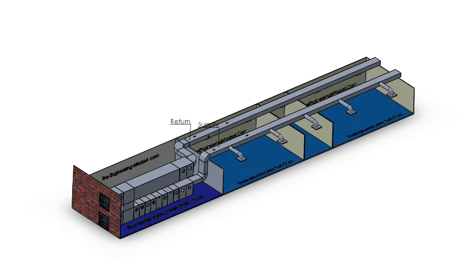CAV systems do have some limitations because their supply air temperature is varied but the volume supply of air is constant. So while this system runs, it provides air at a consistent and constant volume and only the temperature of that air changes. Typically the air is provided at around 13 degrees Celsius, 55 degrees Fahrenheit, but this can be adjusted to suit the needs of the site. The volume is constant, but the amount of air it provides is really going to depend on the size of the area you're conditioning the air for and what's happening inside those rooms, which will dictate how much air needs to be sent.